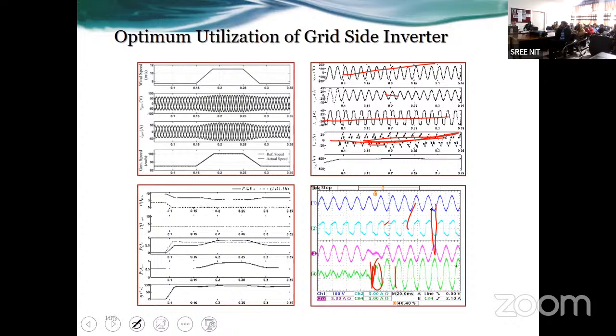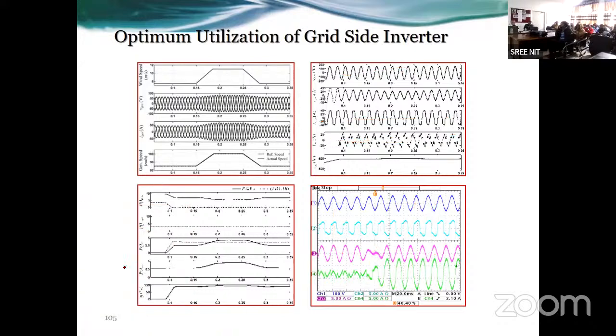But on this side, they are in the same phase. Same phase means you are taking power from the grid. Phase reversal means you are injecting power into the grid. And at this instant, momentarily, this is almost zero, because the load current profile is almost equal to this profile. So if you apply KCL, you will get the answer. Things understood.